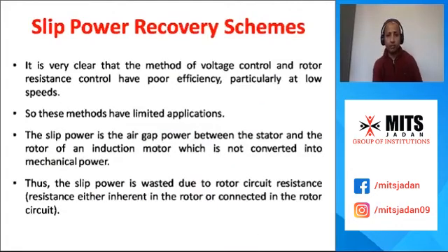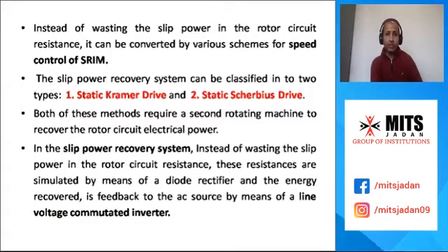Basically, when we are using a slip power recovery system, instead of wasting the slip power in the rotor circuit resistance, these resistances are simulated by means of a diode bridge rectifier, and the energy which is recovered with the help of this is fed back to the AC source by means of a line voltage commutated inverter.